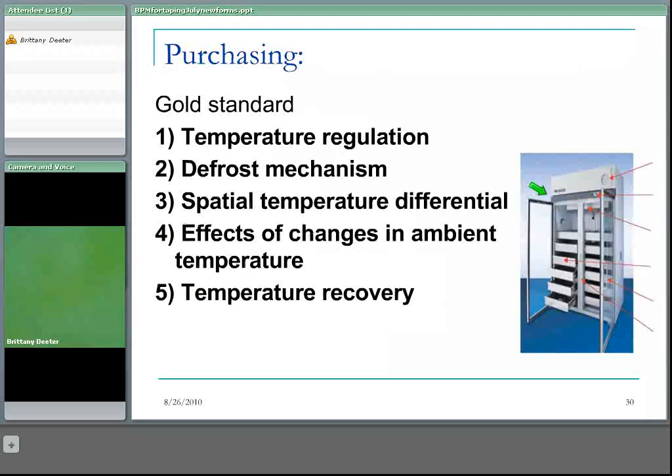Where a purpose-built refrigerator is more effective than a standard kitchen fridge is that it is better at temperature regulation. The mechanism has a very tight temperature tolerance and a quick reaction time to temperatures outside of the set range. A temperature probe for the vaccine control is usually found in the path of return airflow, therefore measuring the temperature of the warmest air in the refrigerator.